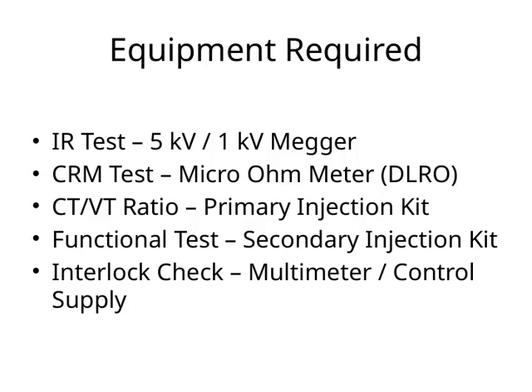Let's go over the equipment required for these tests. First, for the IR test, you'll need a 5 kV or 1 kV megger. This device is essential for measuring insulation resistance, helping us ensure the insulation integrity of the equipment. Next, for the CRM test, a micro-ohm meter, also known as a DLRO, is used to measure low resistance values, which is critical for checking the condition of connectors and bus bars.